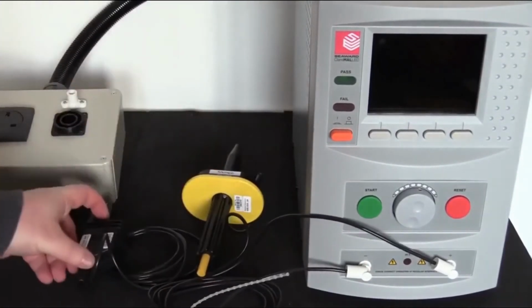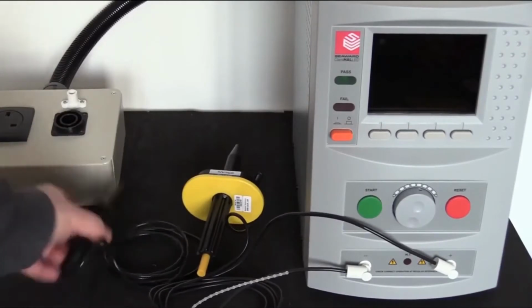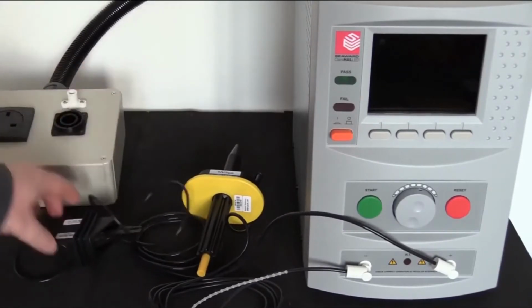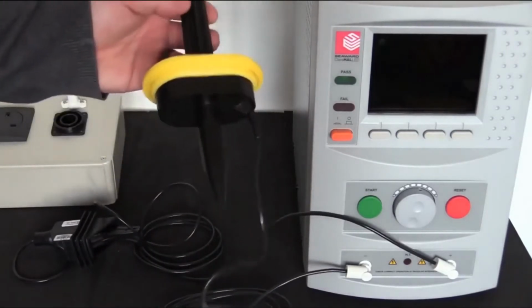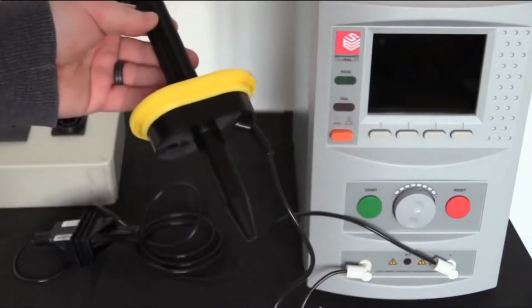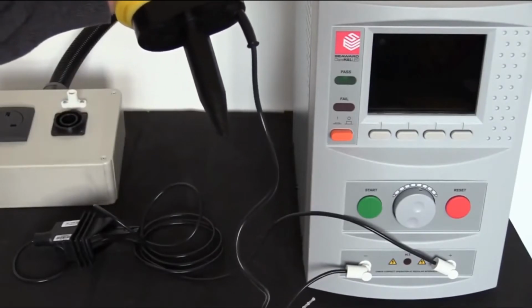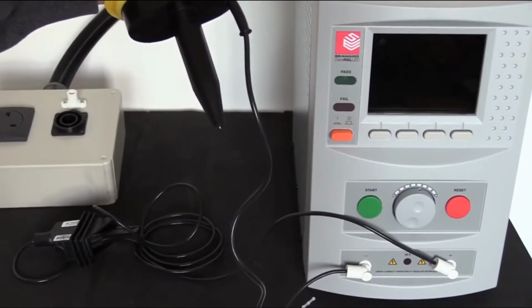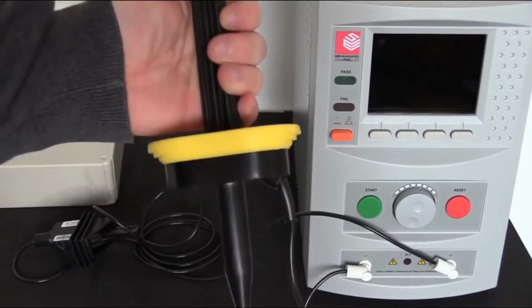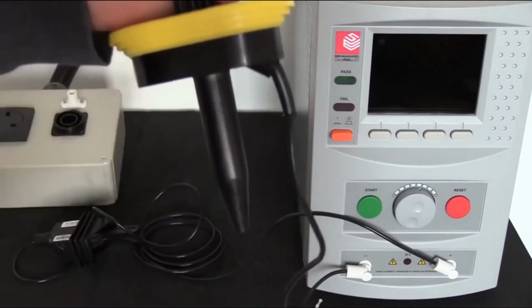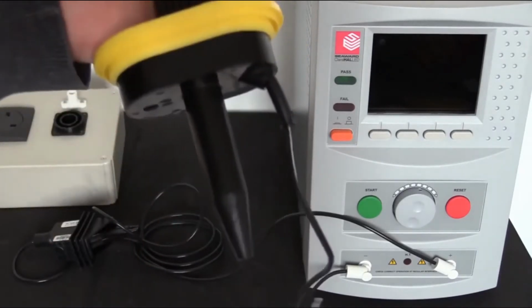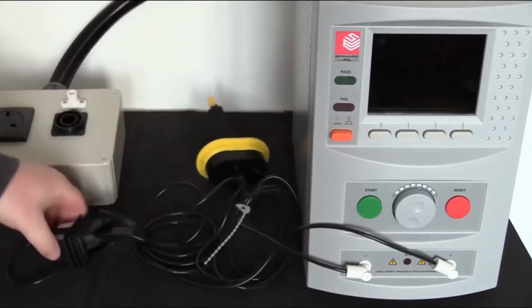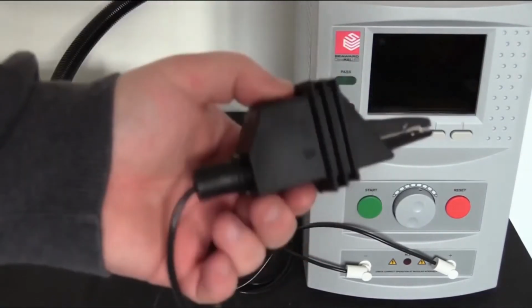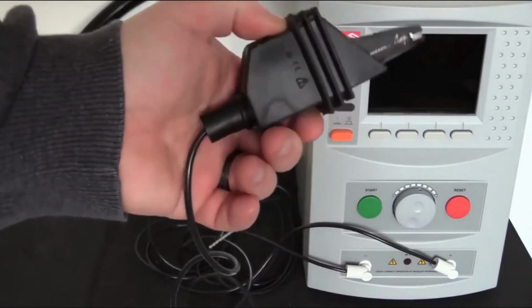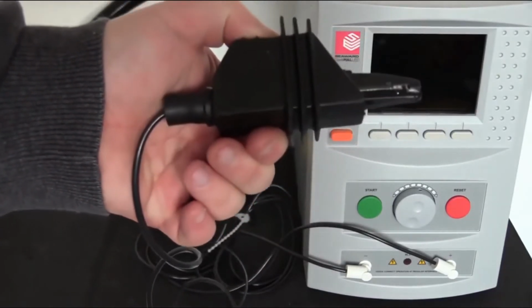When performing tests, we have the Hipot voltage being applied via the clip, and then we simply use the probe to make the test point for the return. The probe itself is spring loaded, so the tip is only displayed when the button is pressed at the top of the probe. Again, this is for safety, so we have hand guards to stop us coming into contact with the high voltage, and similarly on the clip we have a rubberized finger protector to stop us getting too close to any output voltage.